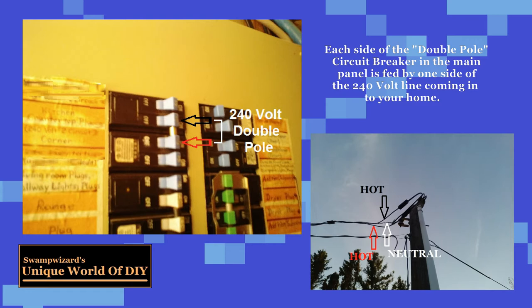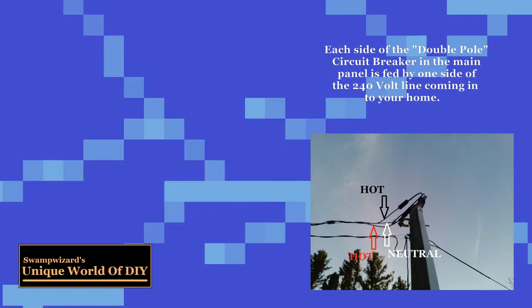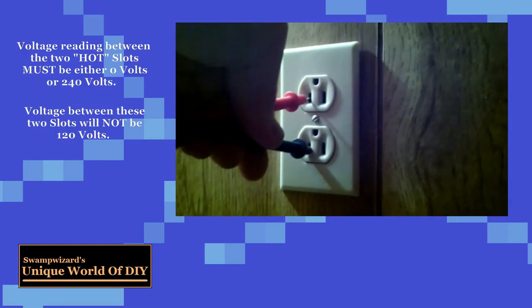Or you may find something where they've used two separate single pole breakers that may not even be located beside each other in the panel. That's wrong, it's not to code, but it doesn't mean somebody wouldn't have done it. So that's why you gotta check the top half and the bottom half before you just assume that the power's off and pull the thing out of the wall.